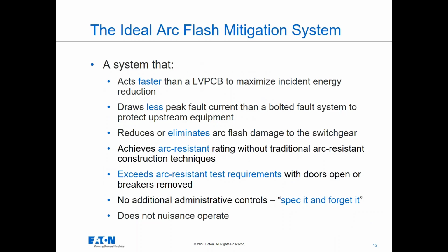given that we've kind of discussed a bunch of different technologies and methods that exist today to counter the incident energy? Well, a system that acts faster than a low voltage power circuit breaker's four cycles, or some manufacturers come in at 3 cycles, would be ideal. You would want a system that, unlike a bolted fault, draws less peak fault current to protect your upstream cable, your upstream transformer windings, and anything that may be improperly installed that could cause a secondary arc fault if something were to come loose, like a poor termination on a cable.